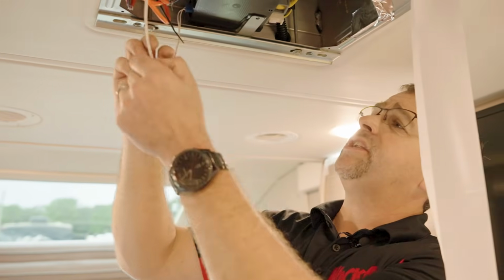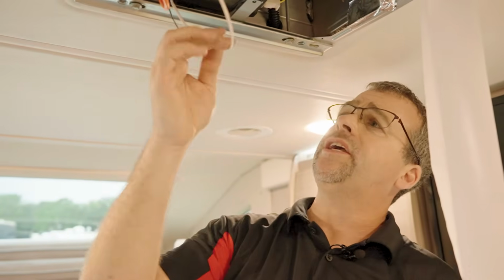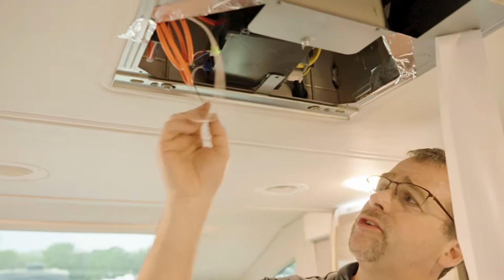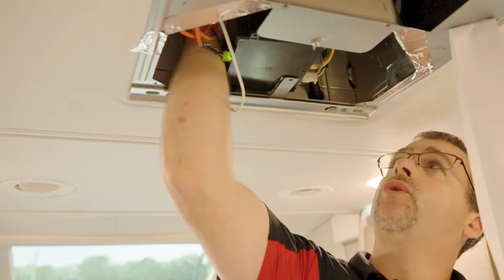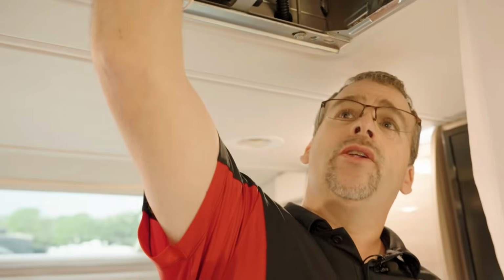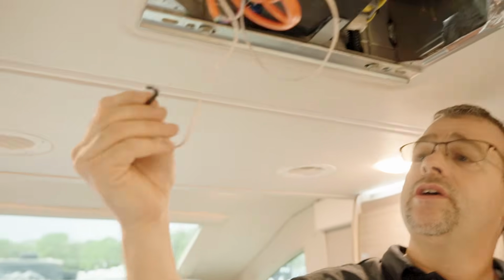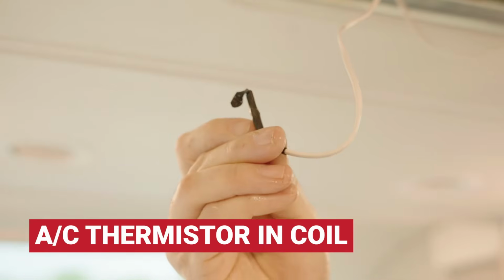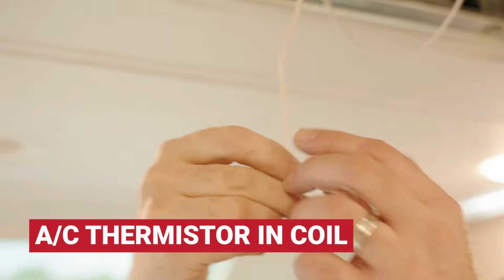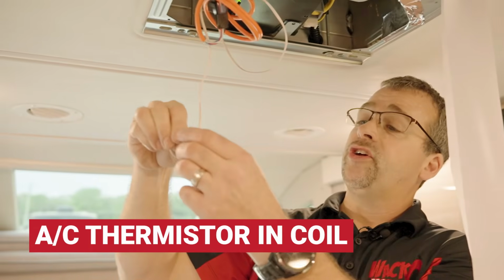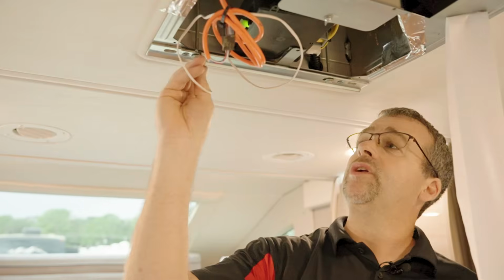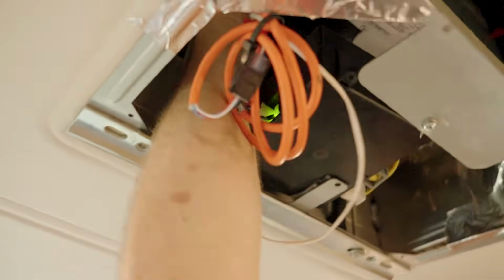Usually in a Dometic, you'll see a white or light gray wire coming out of the control box that goes all the way up into the coil. The nice thing is this one was installed—I'll pull it out and show you what it looks like. Looks like somebody cut off a wire and put a piece of tape on it. That's actually your thermistor; it will turn that compressor on and off so your coil doesn't freeze up. So we're going to put it back in there because that's where it should be.